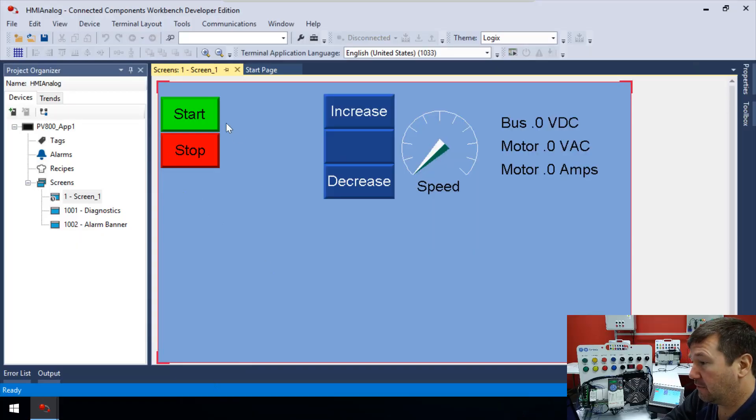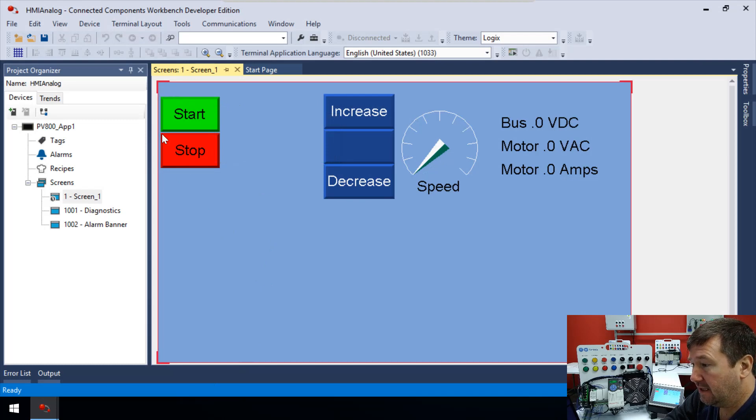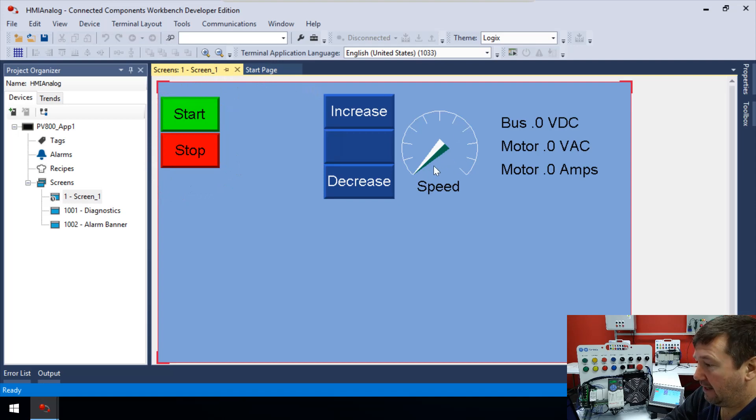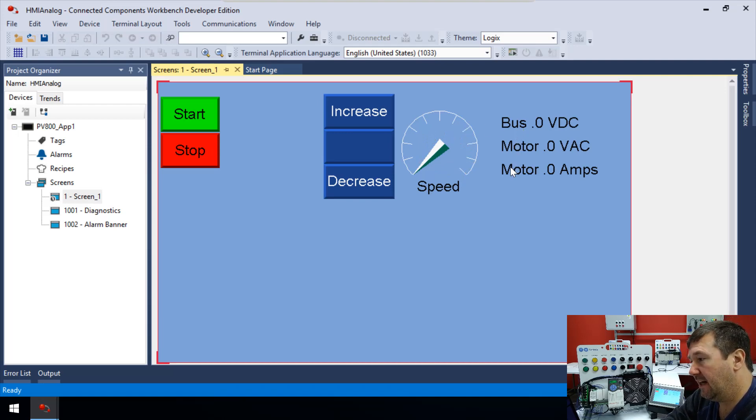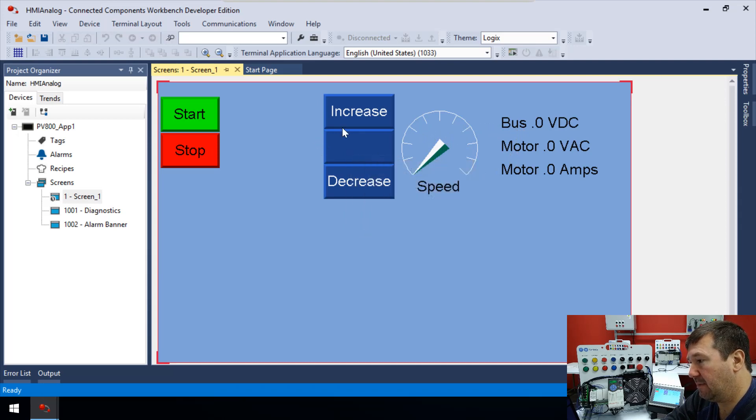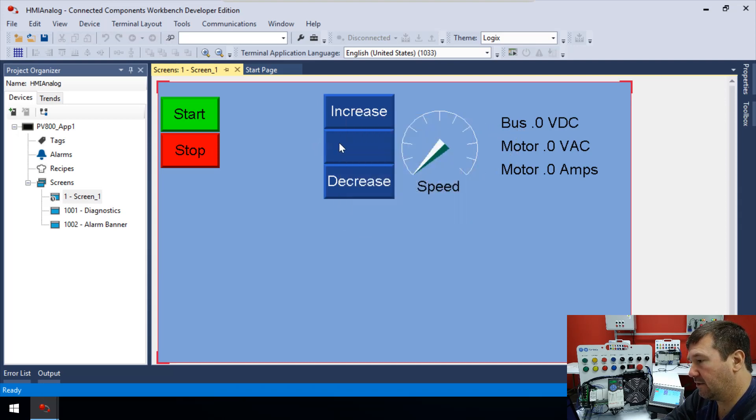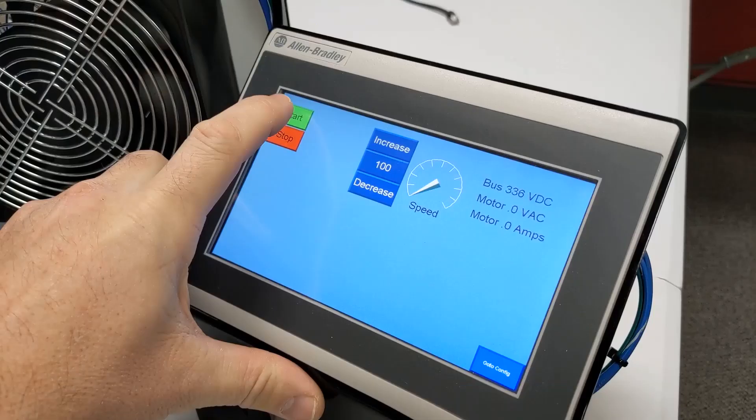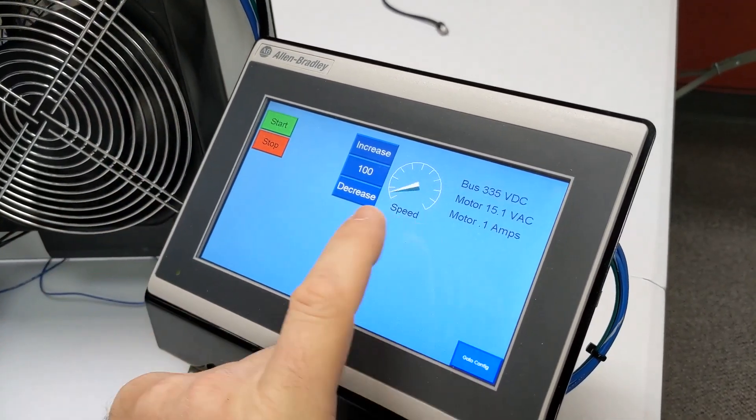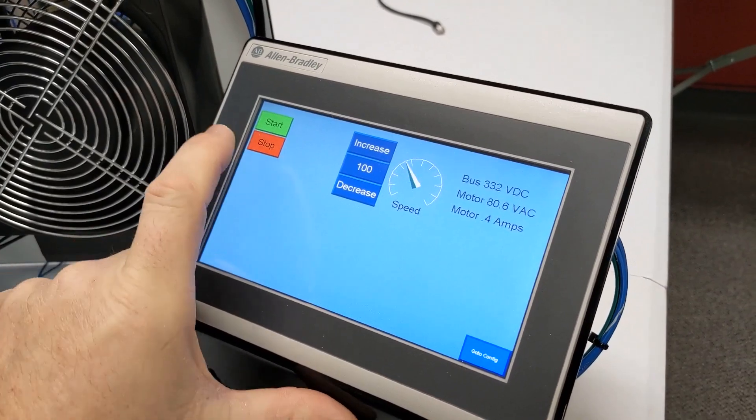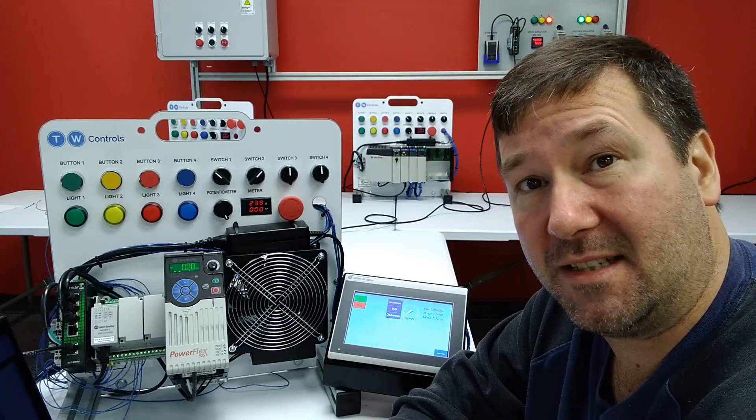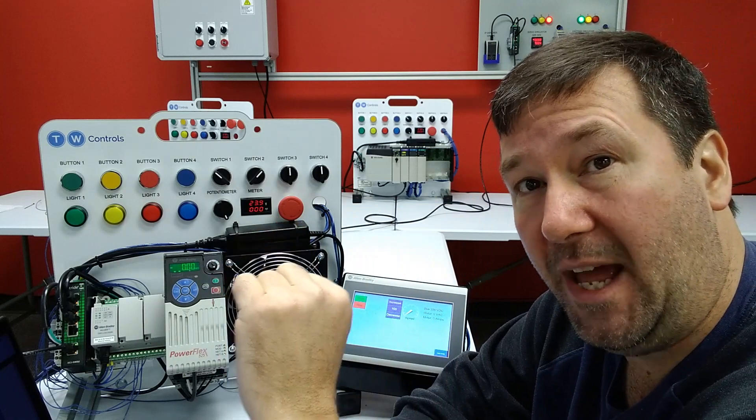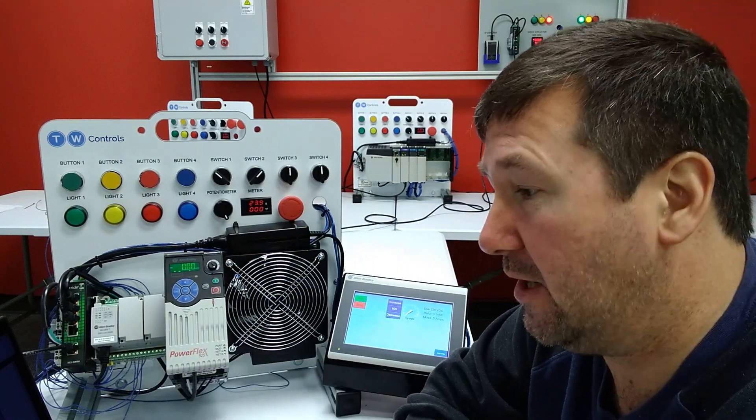In our previous videos, first we configured our tags and communications, and then we added these start stop buttons. And then in the last video, we added this analog gauge to read our drive speed, plus our bus voltage, motor voltage, and motor amps. And then we gave ourselves a way to change the speed, either by entering a value or use our increase and decrease buttons to bump the speed up and down. But a lot of times it's nice to be able to see a historical view of what it's done in the past. So that's what we're going to add now is we're going to add a trend.